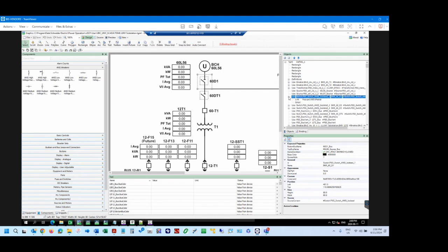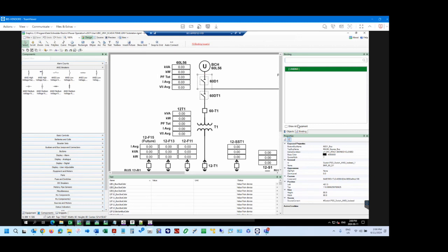So this is an example where you did not have to recompile and rerun it. There's no recompile at all to do with the graphics, actually. All of these saves that I'm doing, the only thing you would need to recompile for would be, let's say you had added new tags that you then wanted to link into new graphic pieces. But once you've populated your tags list and you have them all here in the equipment list, anything beyond this, you don't need to recompile.